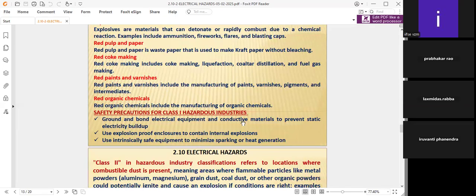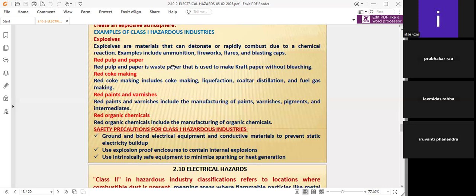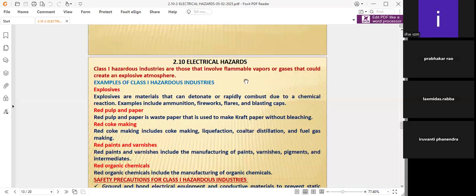Safety precautions for class 1 hazardous industries. First, ground and bond electrical equipment and conductive materials to prevent static electrical buildup. Second, use explosion-proof enclosures to contain internal explosions. Use intrinsically safe equipment to minimize sparking or heat generation. Because these class 1 hazards are reactive with flammable vapors or gases, definitely that can create an explosion.